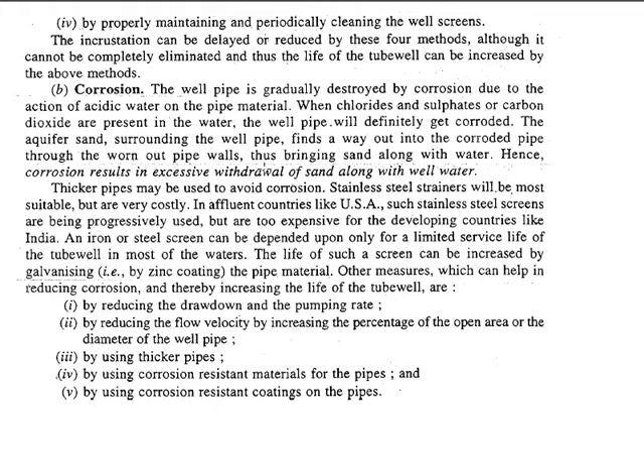To reduce corrosion, we can use galvanized tubewells coated with zinc as the pipe material. Other methods include reducing the drawdown and pumping rate, using thicker pipes, using corrosion-resistant materials for the pipes, or providing proper coating such as zinc coating over the pipes. All such methods can be useful to prevent degradation of the pipe. We conclude these two topics here and will see a different topic next. Thank you.